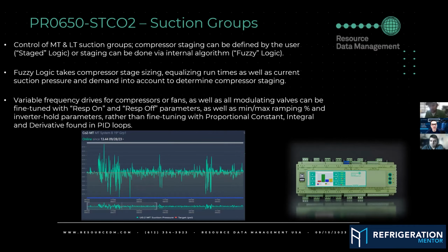Yeah. And I like that you don't just change stuff and then change it again 3 minutes later, and again 3 minutes after that, because you need to see the effects of it. Especially the flash gas bypass valve or the high pressure valve, that affects all the other valves. That's changing your flash tank pressure, your receiver pressure. That's going to affect all your medium temp valves, your low temp valves. So you got to wait and you got to watch it.